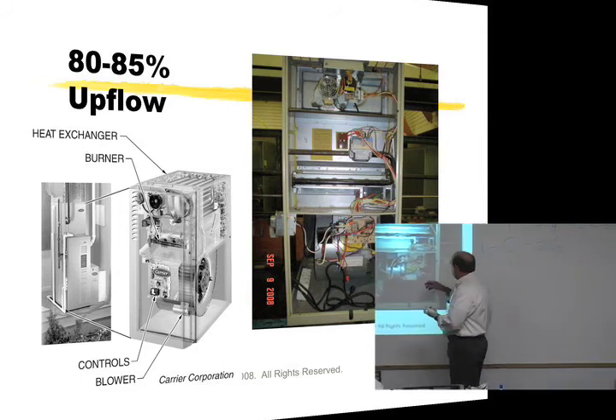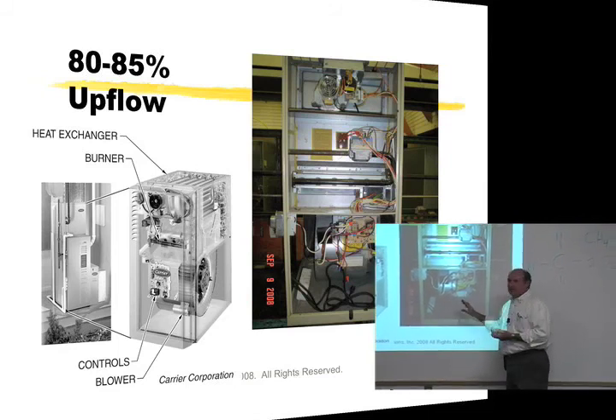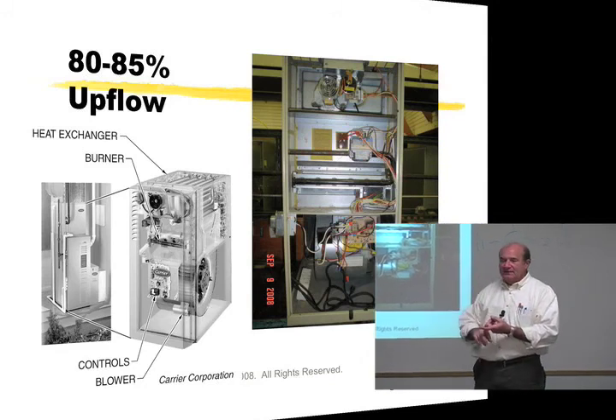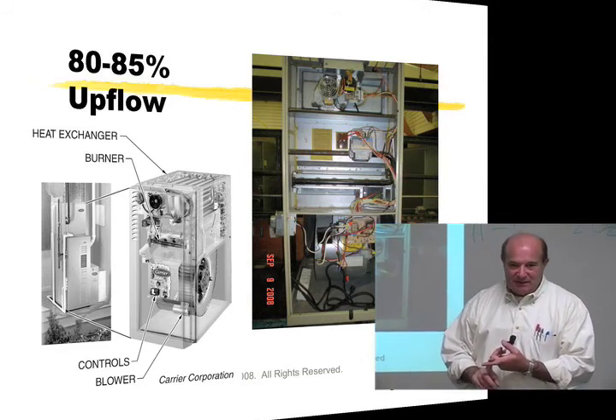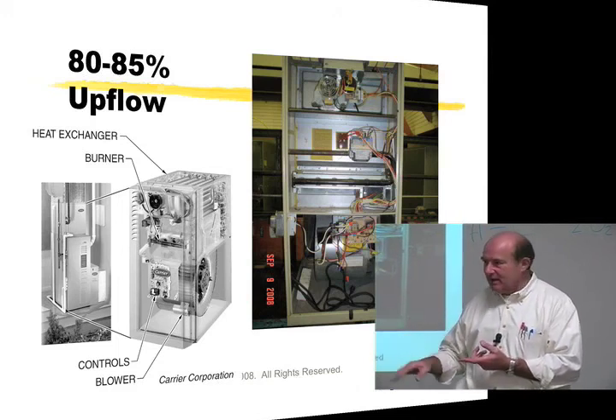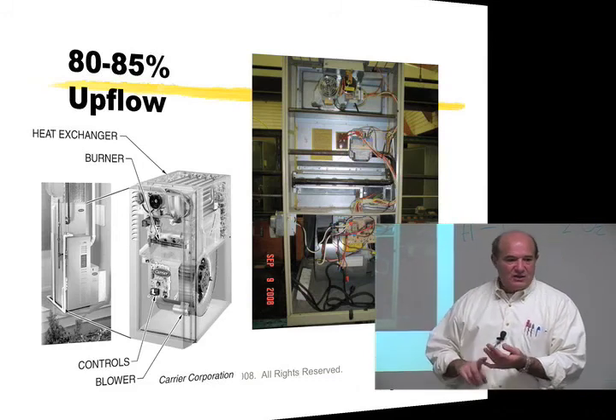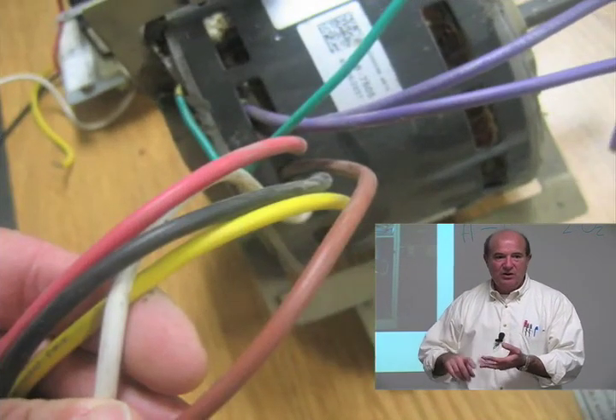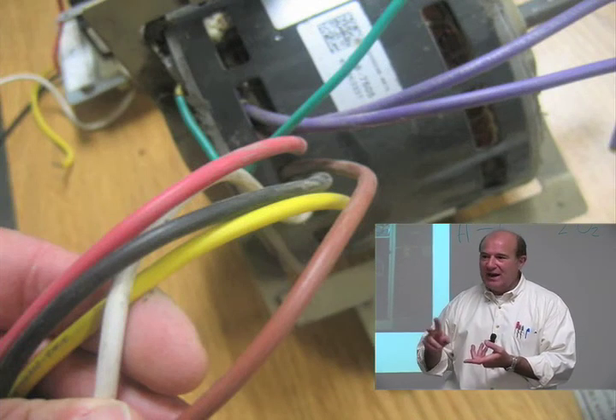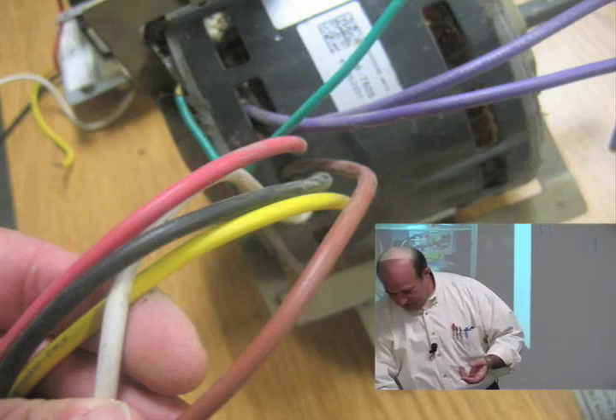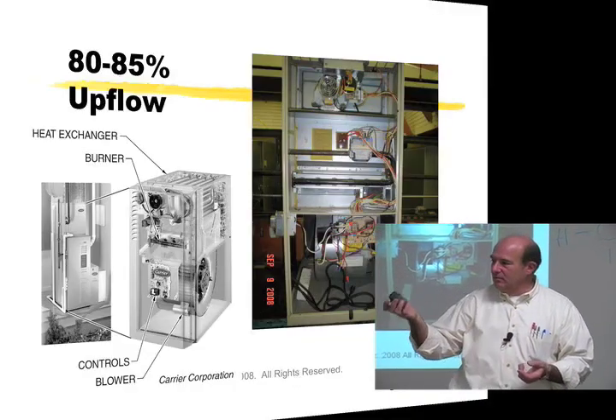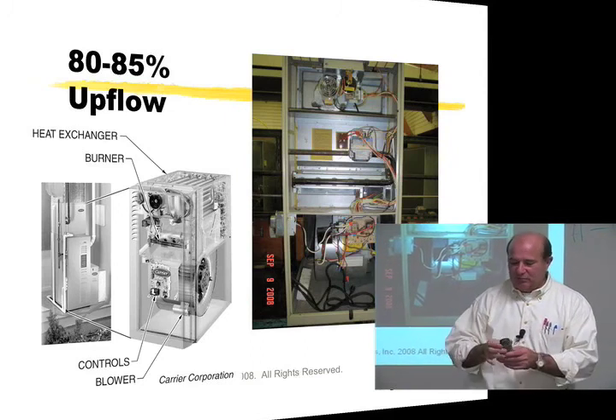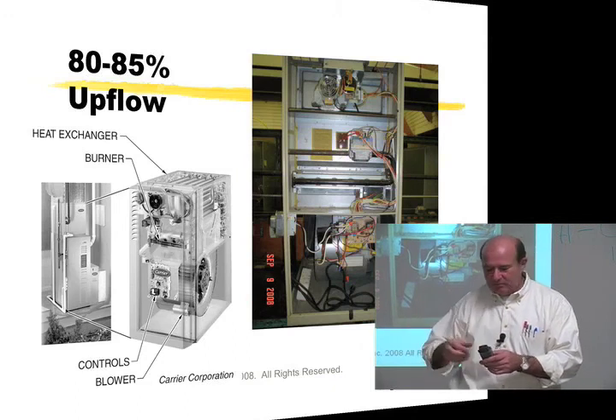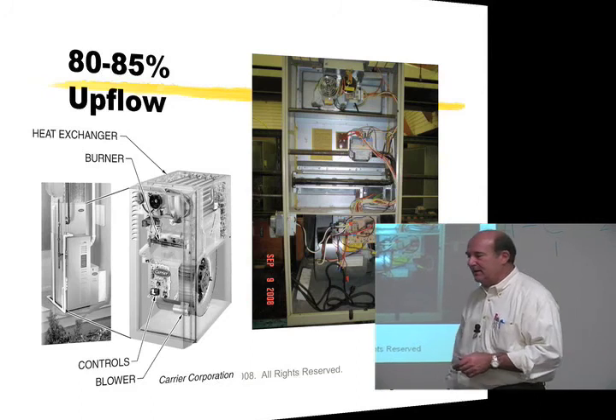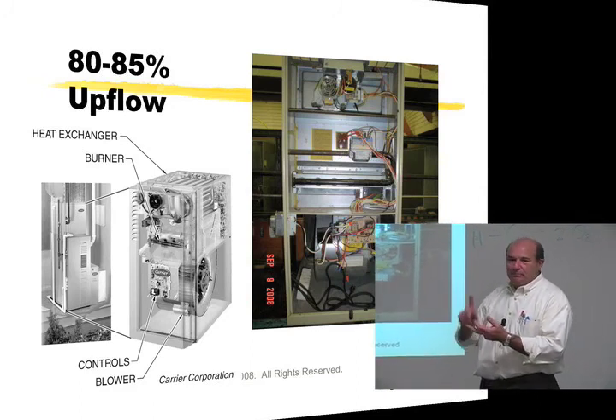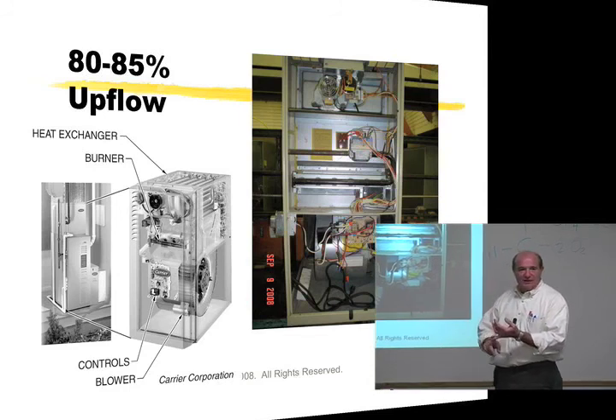So we can select that by taking one of the blower motor leads, and they're typically color-coded. Black is almost always, and I've never seen one that wasn't, but can't swear on everything, but black is almost always high speed. Red is almost always low speed. You might have a blue and a yellow or a brown. Typically brown is the capacitor on the system. And here's a start capacitor that is on a blower system. And typically brown or purple goes to the capacitor and back to the blower motor to get the blower motor started up. But typically black high speed, blue medium high speed, yellow medium low speed, red low speed.